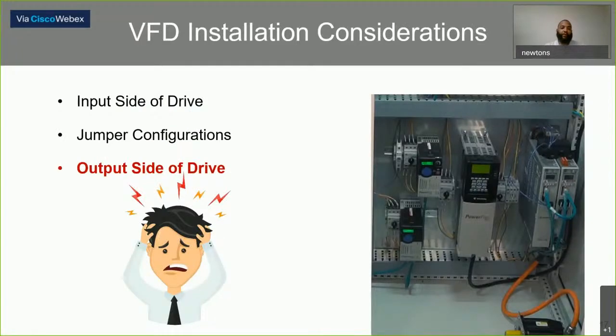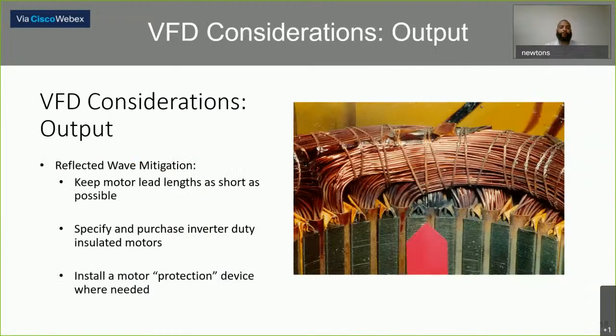And then let's discuss the output side of the drive. A couple of considerations that you need to be concerned about with your VFDs is cable length. If you have a very long cable length, you can start running into issues such as cable charging current, and also reflective wave.